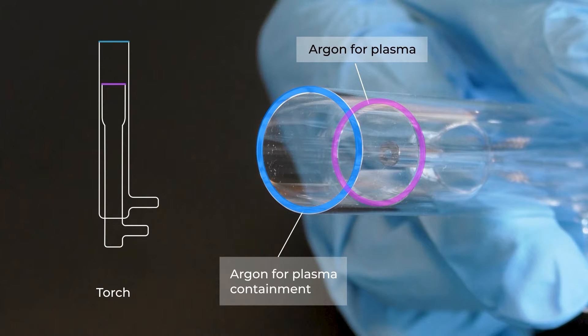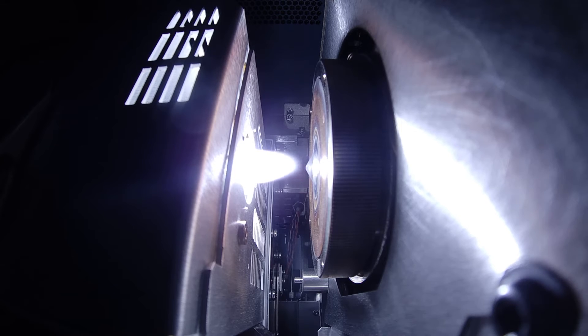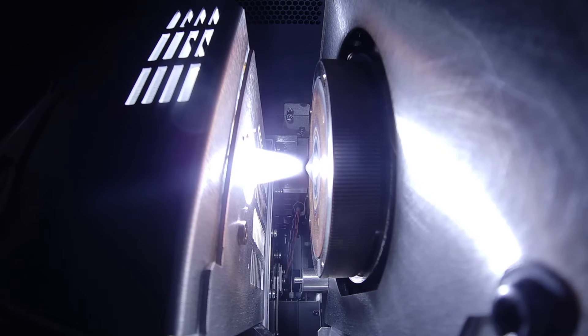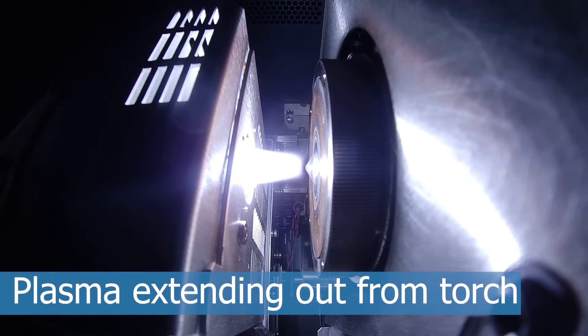The middle cylinder supplies the argon gas that forms the plasma, and the inner cylinder injects the sample aerosol into the plasma. An initial spark ionizes the argon, and the resulting free electrons and argon cations are accelerated by the oscillating RF field.